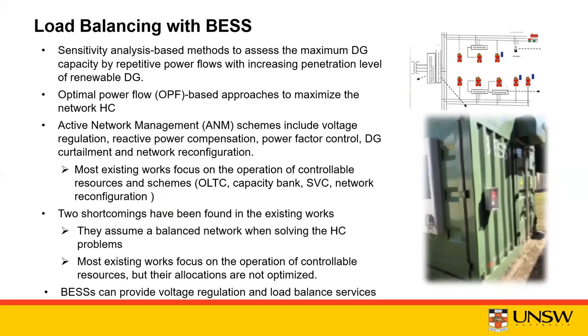This is a photo of the grid battery deployed in one of the suburbs. The approval for the site also takes time. So we do sensitivity analysis to assess the maximum DG capacity by repetitive power flows and increasing penetration level of renewable DG, to find out the maximum hosting capacity, and also to identify weak points or the most effective locations for phase switching devices and battery energy storage systems.